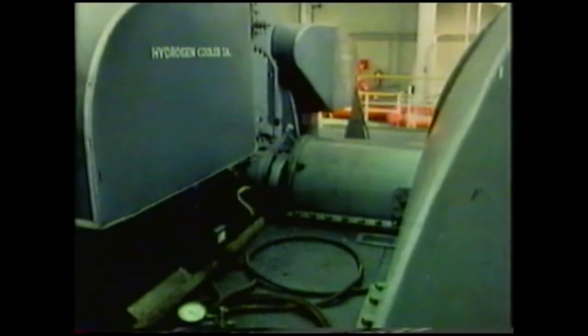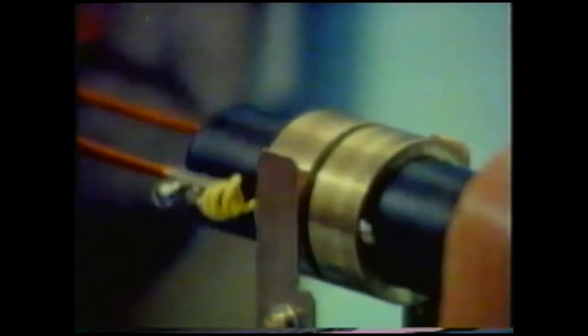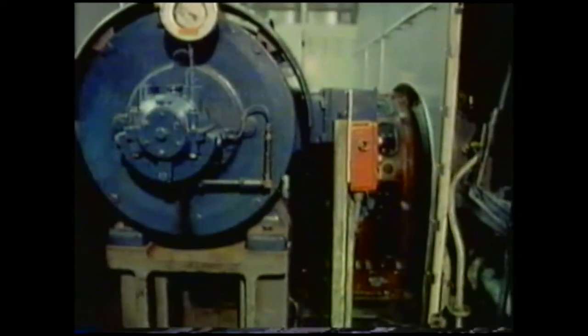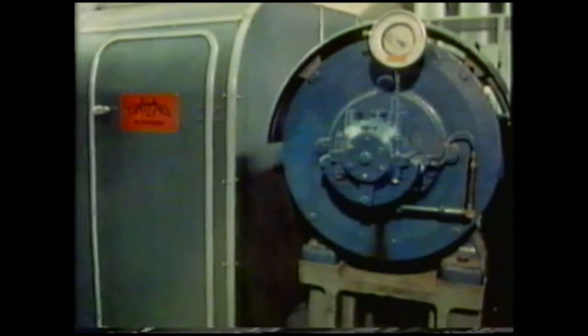They drive this AC generator, which consists of a big electromagnet rotating inside an arrangement of coils. The electromagnet rotates, not the coil as in the lab model, but the effect is the same. The model used a permanent magnet. The big generator uses an electromagnet. So there has to be a sort of mini-generator, called the exciter, to power this electromagnet. Here it is, at the end of the shaft.